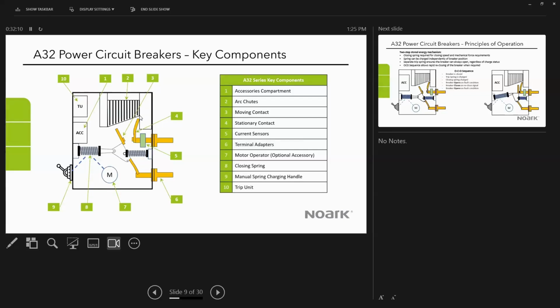There's a charging handle, which is item number 9, just on the lower left-hand side of this graphic. So the charging handle allows you to charge the springs manually by hand. And then there's also something called a motor operator, which charges those springs based on an electrical signal and a motor that winds the springs up. And lastly, there's something called a trip unit, which is an electronic device that works with the current sensors you see on the right-hand side in green. The trip unit and the current sensors work together to sense the current flowing through the breaker, and it provides all of the tripping functions that we'll talk about in a bit.